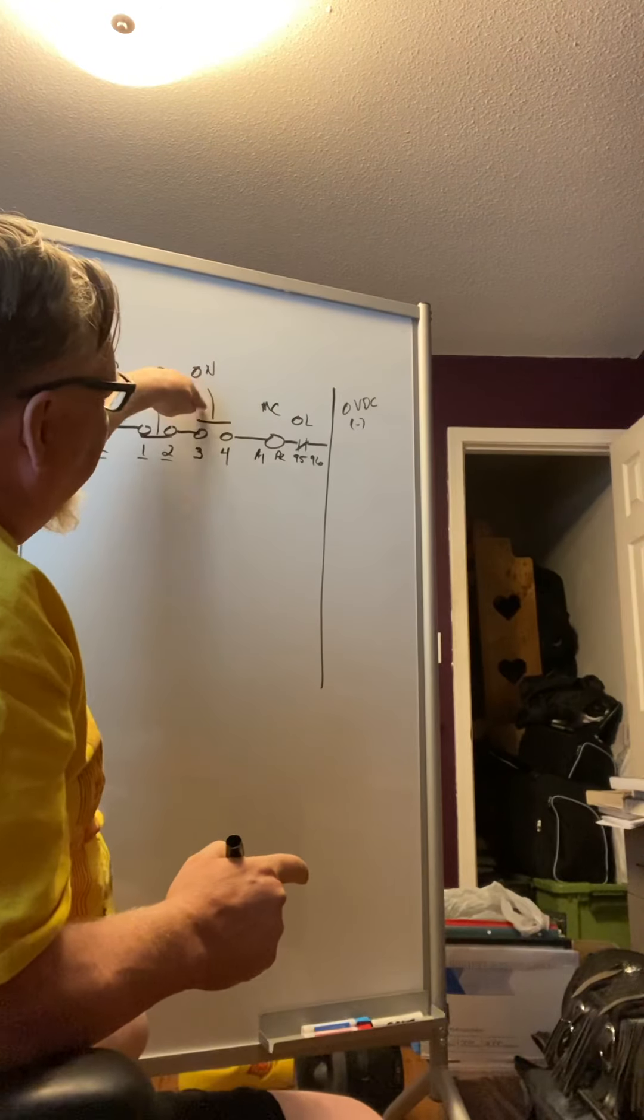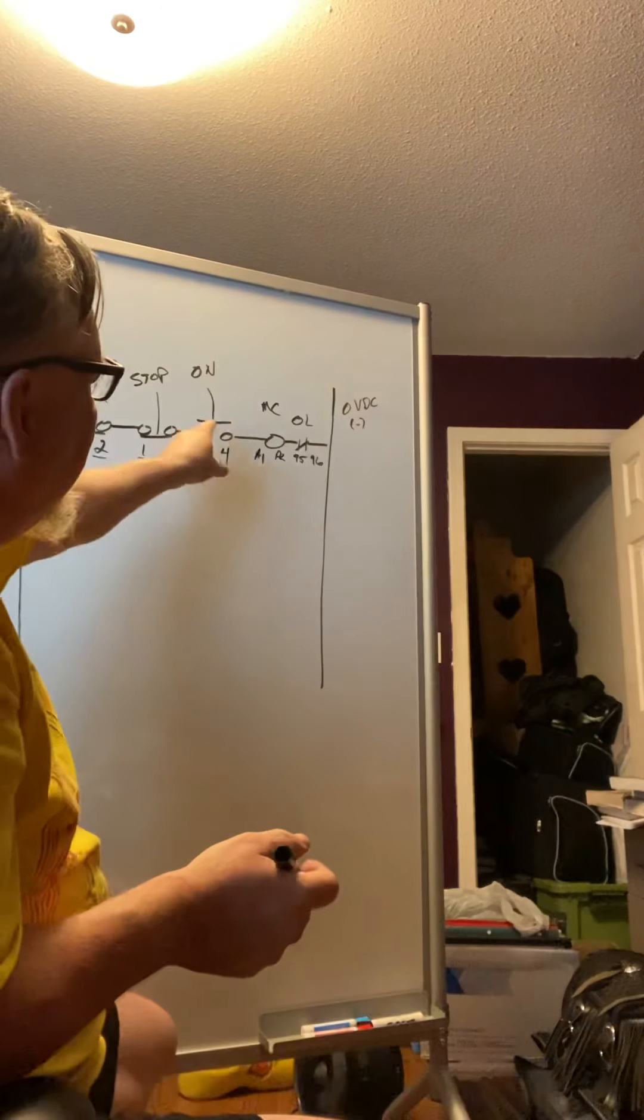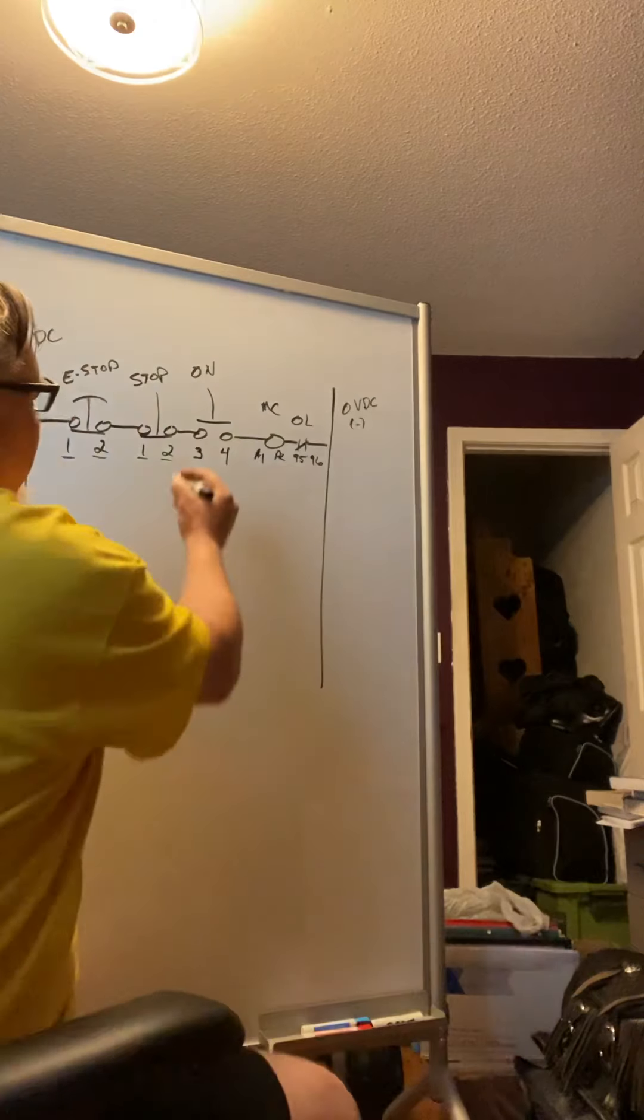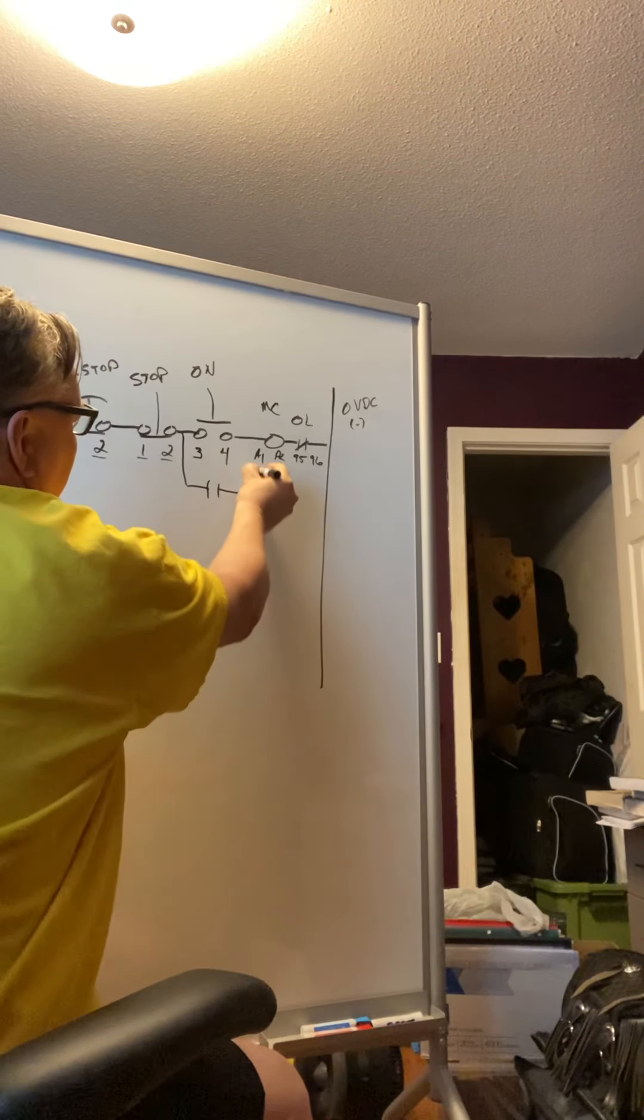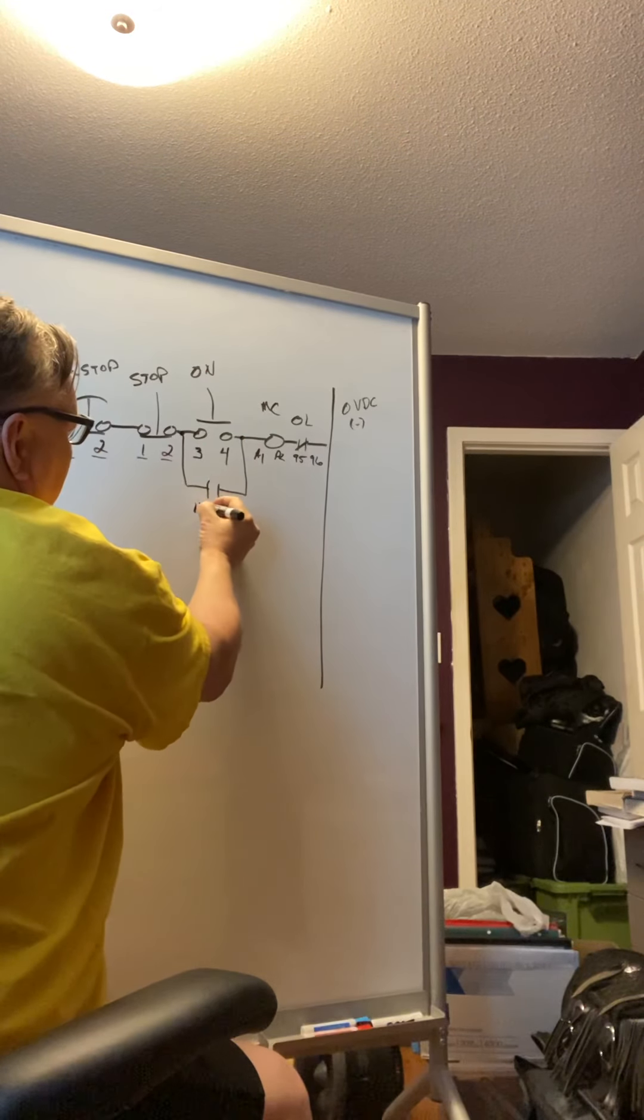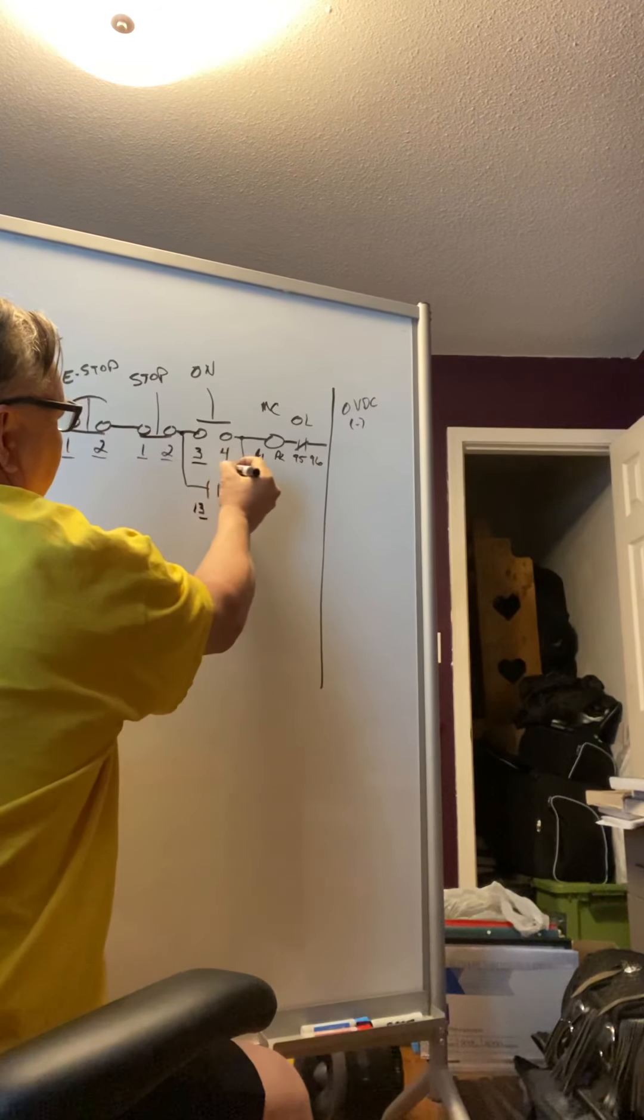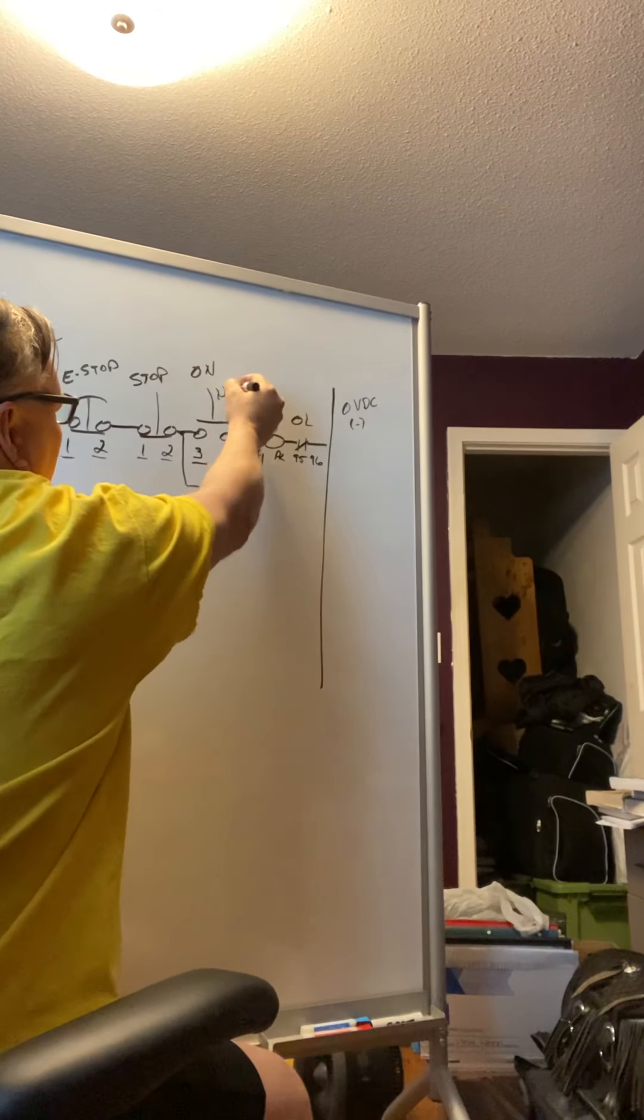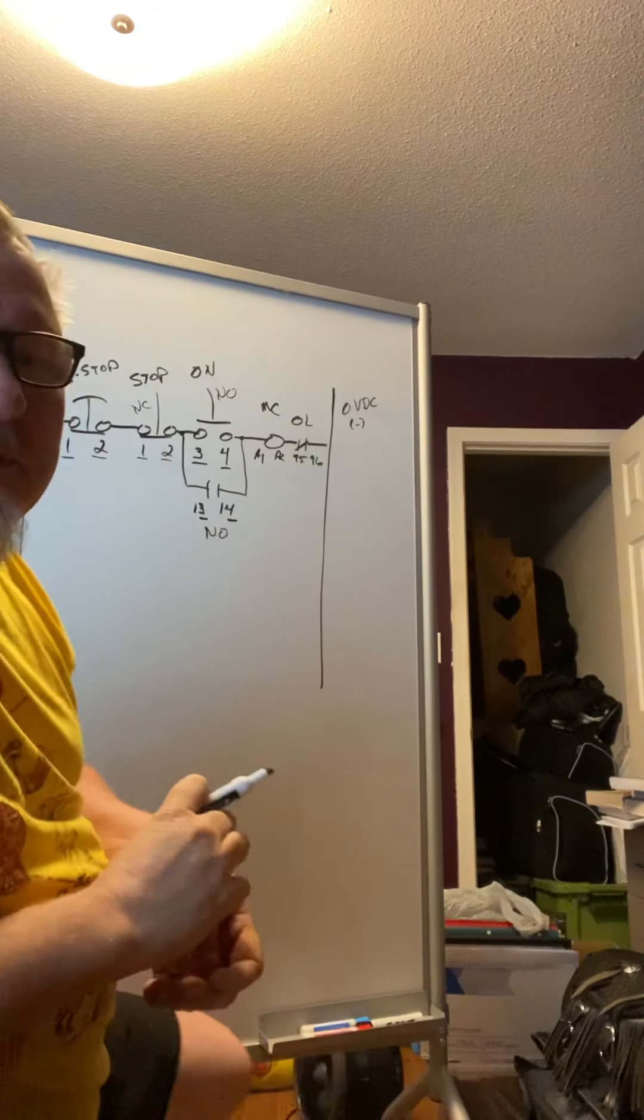Now there's one piece that we're missing right now for this to work right now. If we press this switch, the contactor would come on and the motor in itself would come on. But as soon as you let that switch up, it would stop. So what we need is a latch and that latch comes down here like this. And this is going to be 13, 14. And if you'll notice the three, four, this is normally open. This is normally open. This is normally closed. Normally closed.